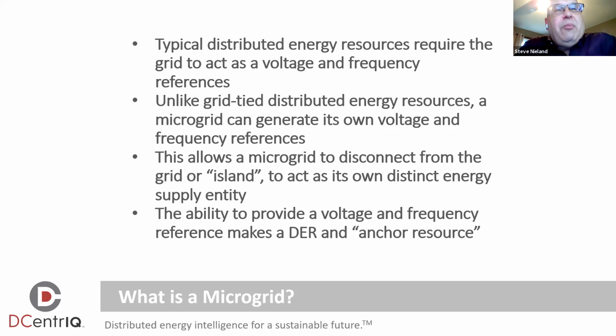So if you have a power plant, you need to be able to do something called a black start. A black start is that ability to have this reference we're talking about. So if I'm the power plant, for instance, and the grid goes down, there's a whole bunch of safeties that drop in because I can't keep dumping coal into the boiler, I can't keep generating steam, I can't keep turning turbines because there's no place for any of that to go. So the plant shuts down.